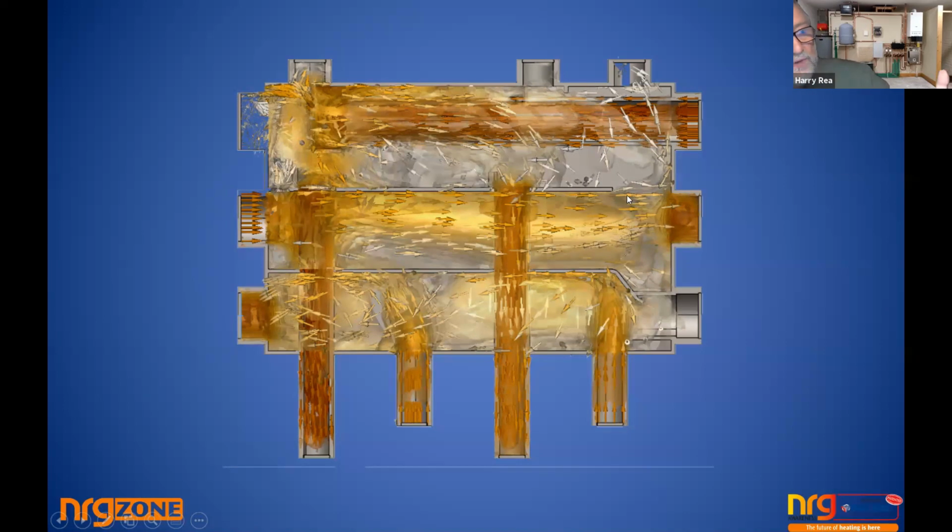If I say to you, I know the flow through on the boiler, I know the flow through on the heat pump, I size my pumps and my flow speeds properly, I know what my zones are doing because I've done my calculations. And at the end of the day, I can actually design a system that before you ever put a screw in the wall, I can tell the person in the house, your efficiencies are going to be through the roof. I would ask anyone to tell me a better way to put two boilers together and keep the efficiencies at that height.